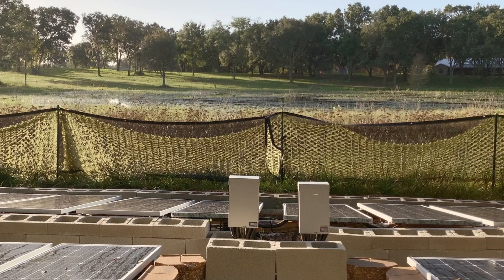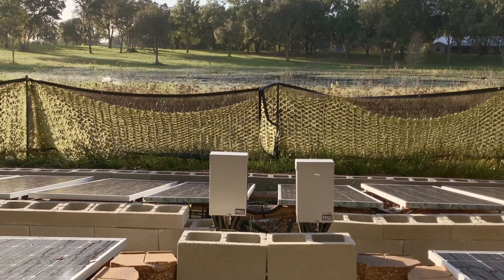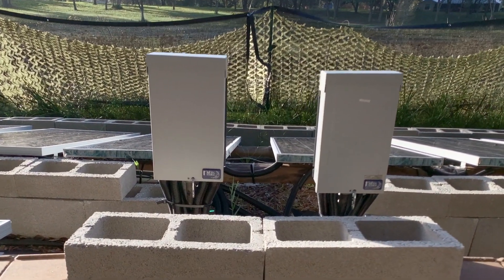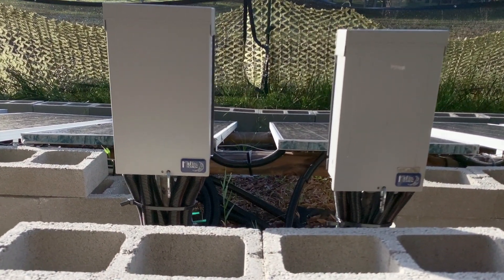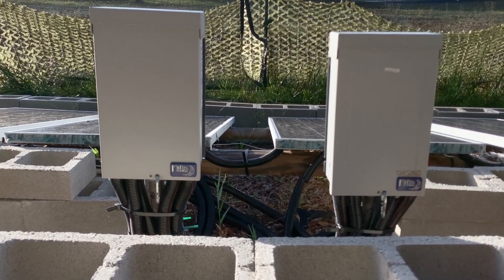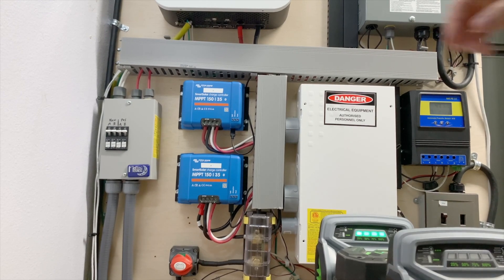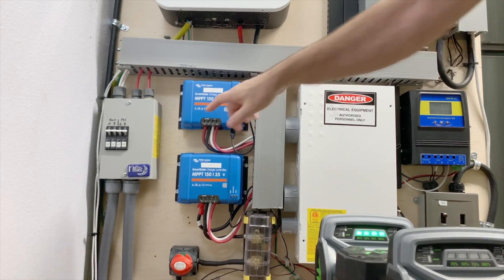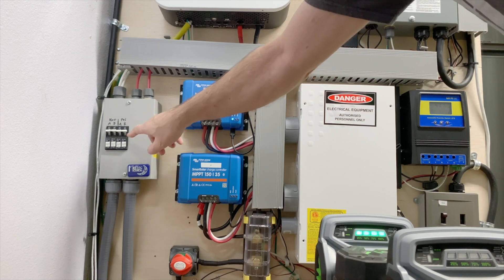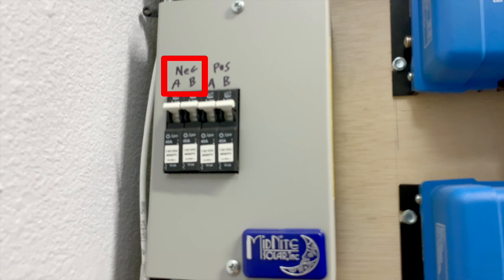The panels are wired together in series into strings. These strings are combined through combiner boxes and the output is sent to the house. We have a positive and negative from array A and a positive and negative from array B, using 8 gauge PV cable. Those cables come in through this DC breaker box from MidNite Solar, and each cable gets its own DC breaker.